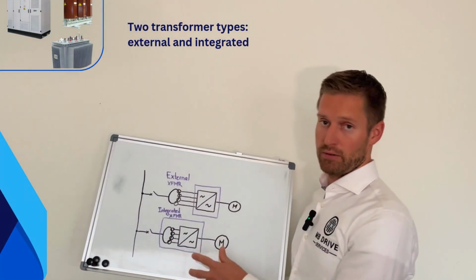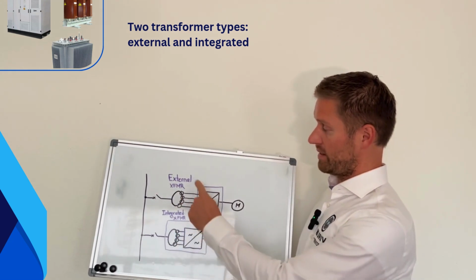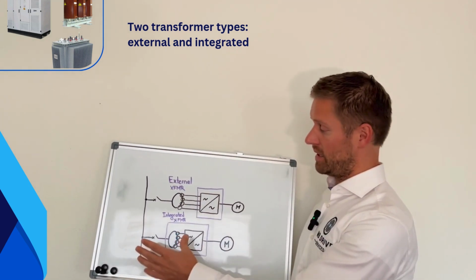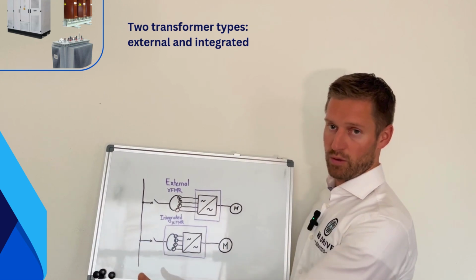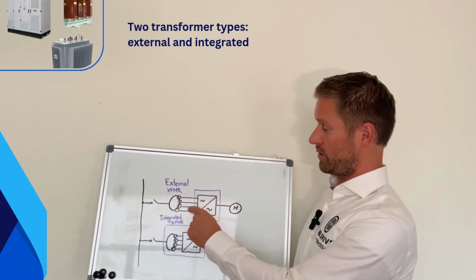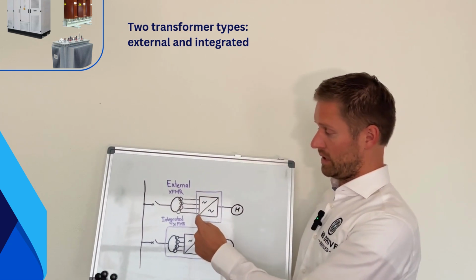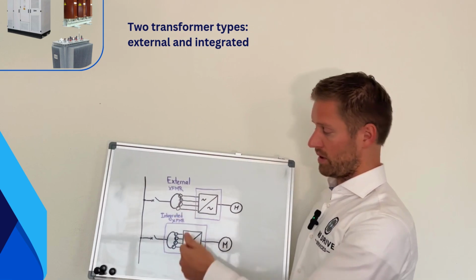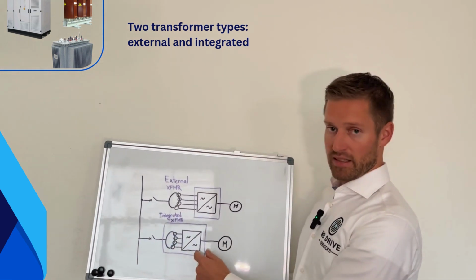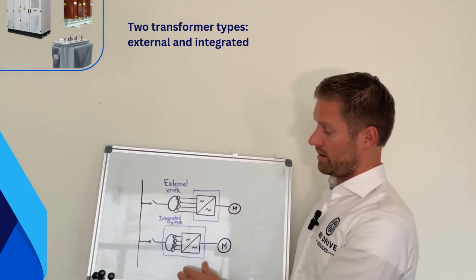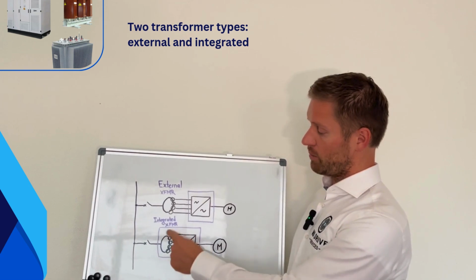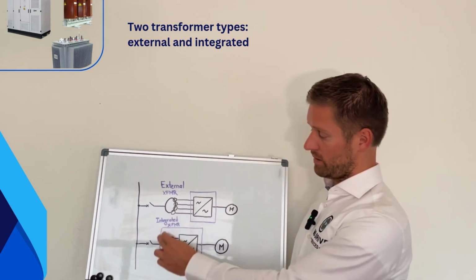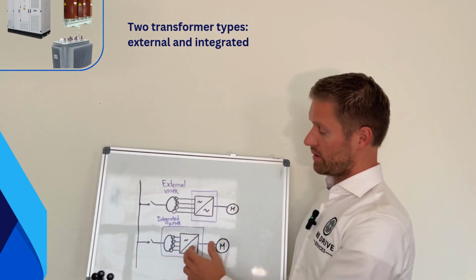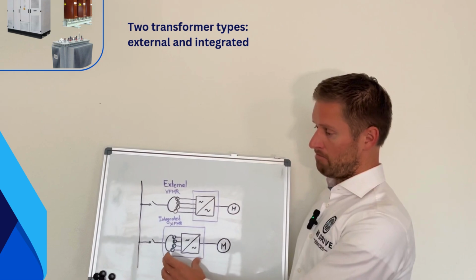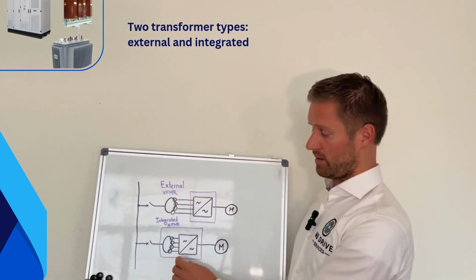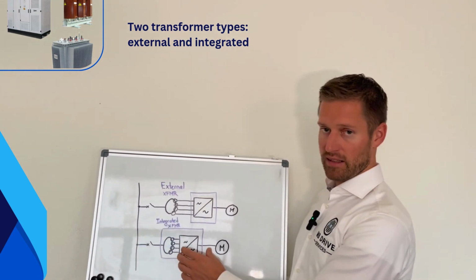So there we have basically two variants. Either the transformer is external, so it's a standalone component separated from the VFD. It can be installed indoors or outdoors and then connected to the VFD, to the rectifier or input section of the VFD, either through power cables or bus bars. The other variant is the integrated transformer, or also called inbuilt transformer. So in that case, the input transformer is actually part of the VFD, part of the product, and it's integrated into the same enclosure. So the VFD enclosure has like two compartments, one dedicated for the transformer and the other one for the VFD itself.